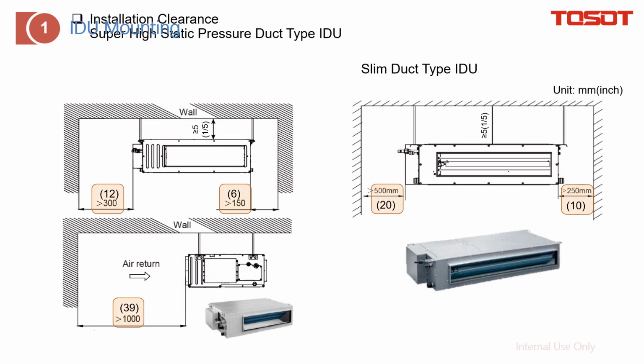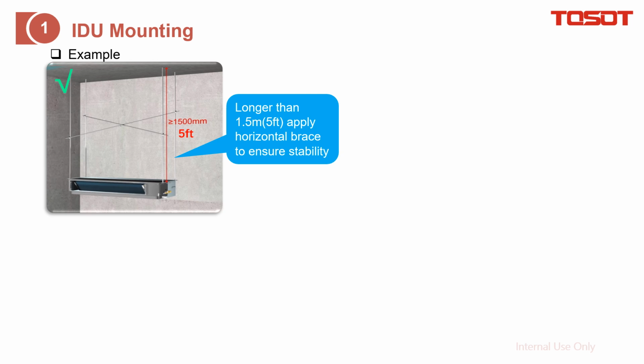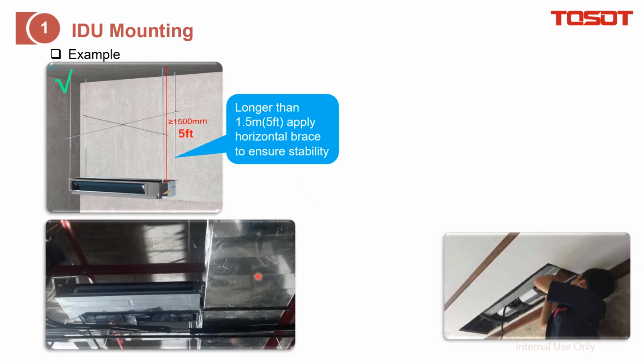And also, this is the super high static pressure. According to the different types of indoor unit, this is the requirement. If the hanger rod of the duct type is longer than 5 feet, we require applying this horizontal brace to increase the strength. This is to ensure stability. In these two pictures, is the installation okay?